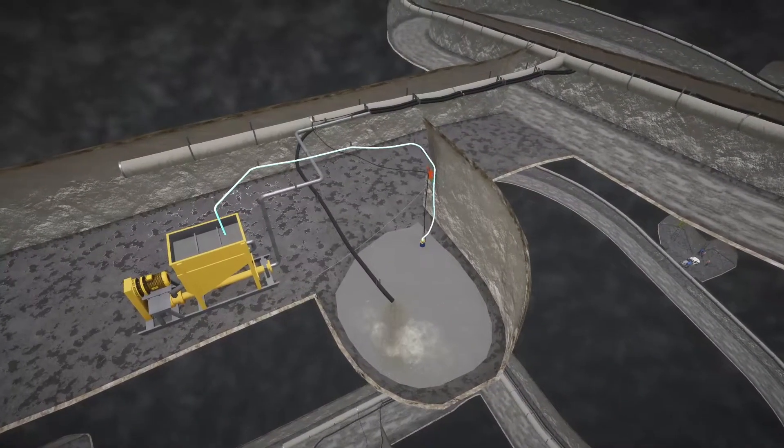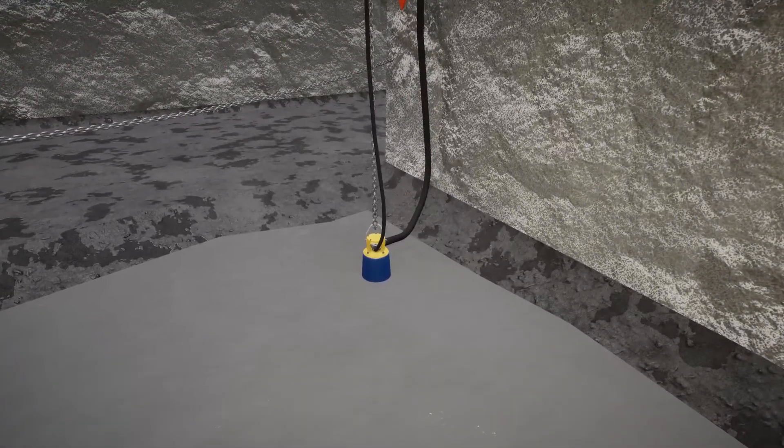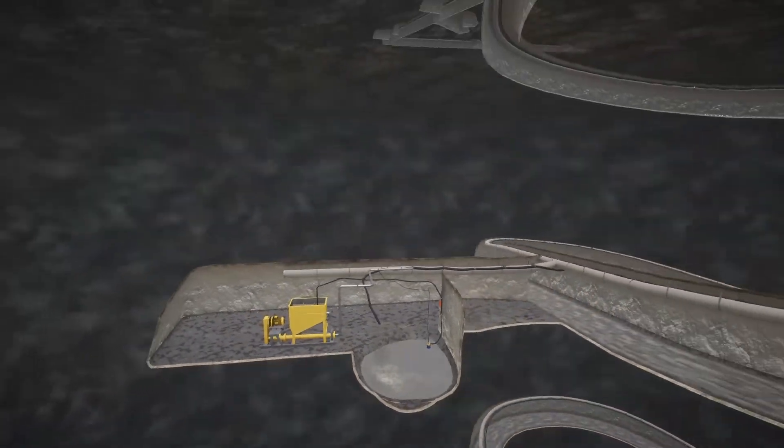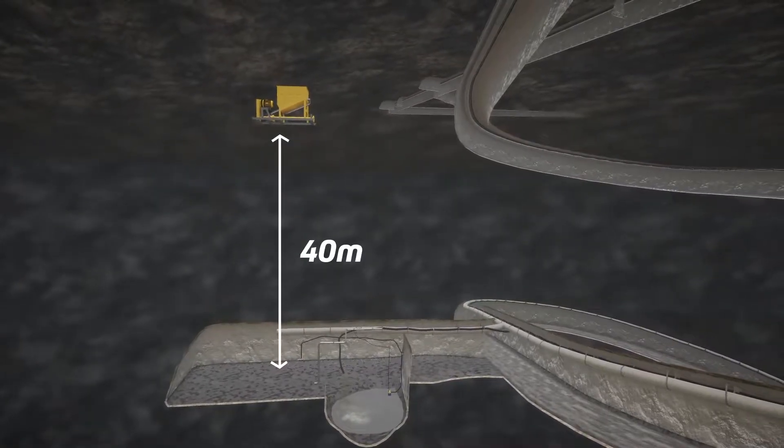A traditional 8 kilowatt submersible pump is designed to operate efficiently at 40 meters of total dynamic head. In this application, this means the helical rotor pump should be positioned here.